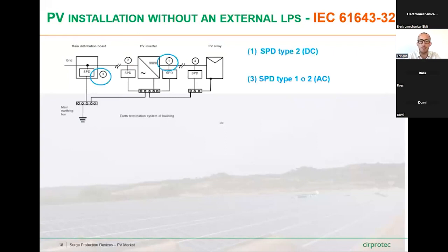The IEC standard states as mandatory to install the SPD in the location 1, close to the PV inverter. According to the IEC, in this type of PV installation, it should be a DC SPD type 2. And then the other SPD defined as mandatory to install is the one in the location 3, close to the main distribution board. This one is an AC SPD type 1 or type 2 or a type 1+2, as we've seen in the previous slides.